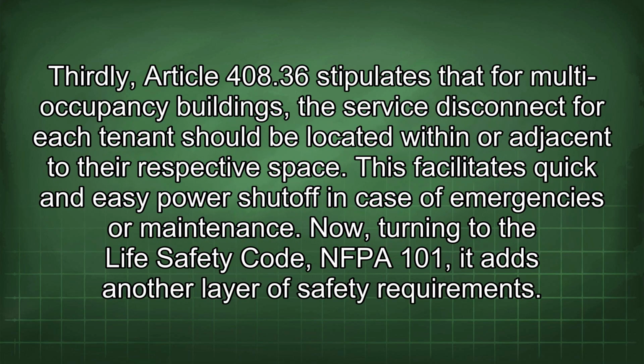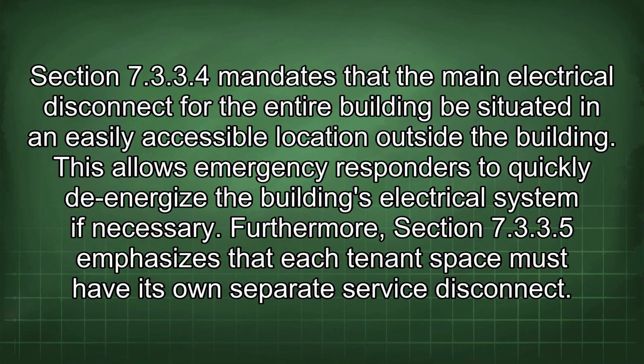Thirdly, Article 408.36 stipulates that for multi-occupancy buildings, the service disconnect for each tenant should be located within or adjacent to their respective space. This facilitates quick and easy power shutoff in case of emergencies or maintenance. Now turning to the Life Safety Code, NFPA 101, it adds another layer of safety requirements. Section 7.3.3.4 mandates that the main electrical disconnect for the entire building be situated in an easily accessible location outside the building. This allows emergency responders to quickly de-energize the building's electrical system if necessary.